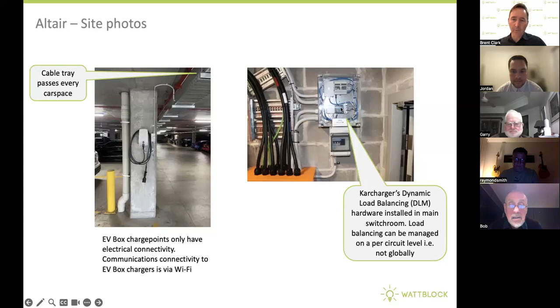Here's an example of an EV box charge point. In the switch room you've got this box, which is dynamic load balancing equipment. It monitors the complete load coming into the building every second and sends out messages to adjust the charging speed for all the charge points so it doesn't overload the building.